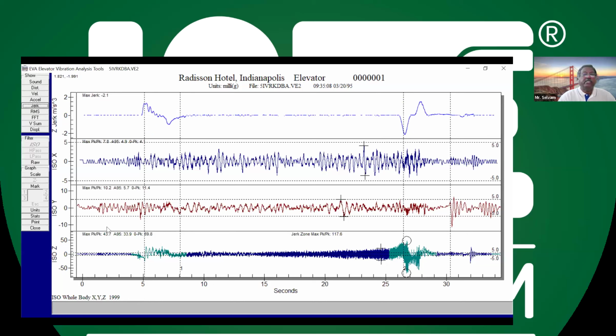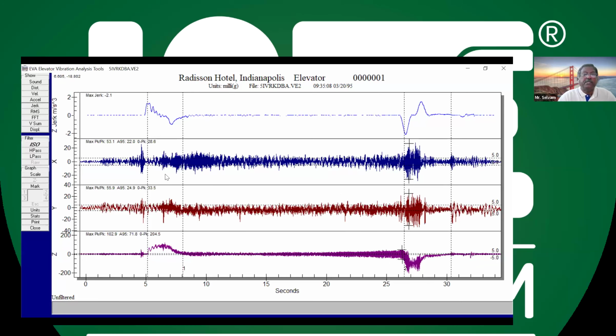Next one is the vibration level, horizontal vibration and vertical vibration. Horizontal vibration, if you see ISO, normally I told you we are capturing up to 100 hertz. For the vibration up to 100 hertz, two types of values are captured. Maximum peak to peak is measured, and average A95, meaning 95% of the time what the value is, that is the bandwidth. So it is about 22. Maximum peak to peak is 53. This is on the front and back. Blue color, this one, X1, is the front and back vibration.